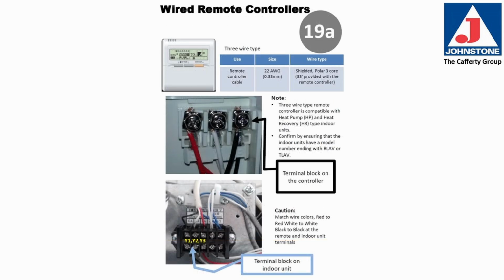Wired remote control connections. Use remote control cable, 22 gauge AWG, shielded, polar, 3-core wire. There's 33 feet of wire provided with the remote controller. 3-wire type remote controllers are compatible with heat pump and heat recovery type indoor units. Confirm by ensuring that the indoor unit has a model number ending in RLAV or TLAV.